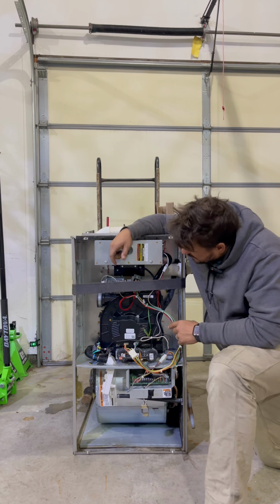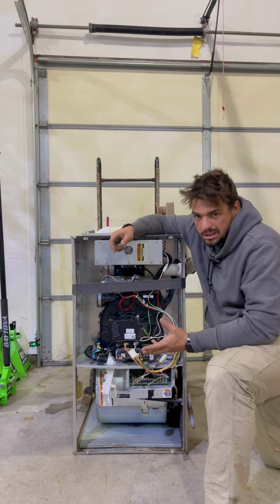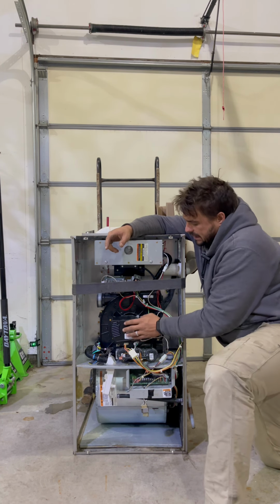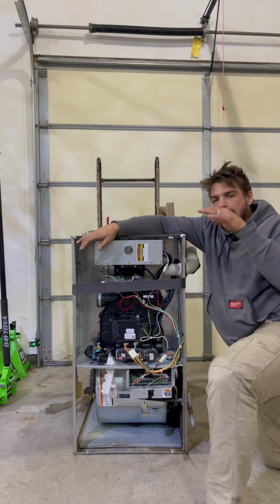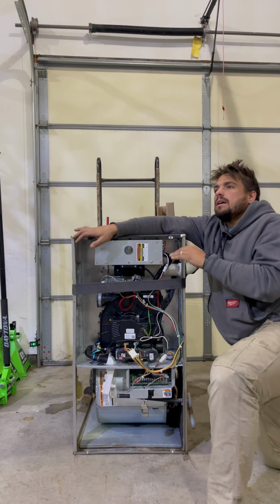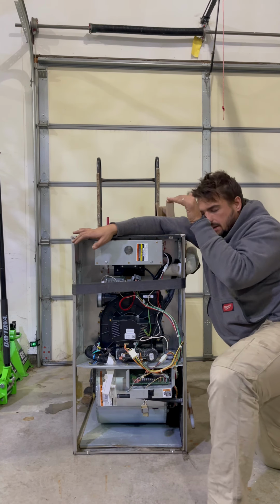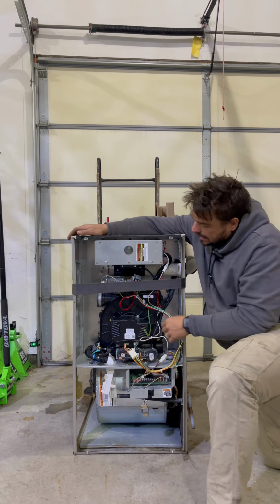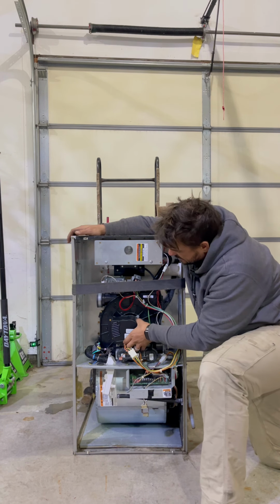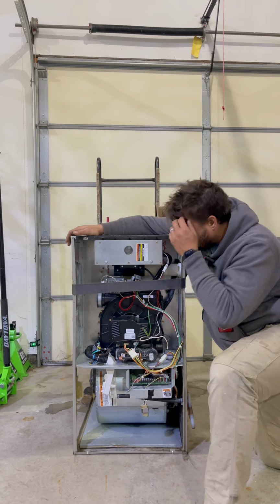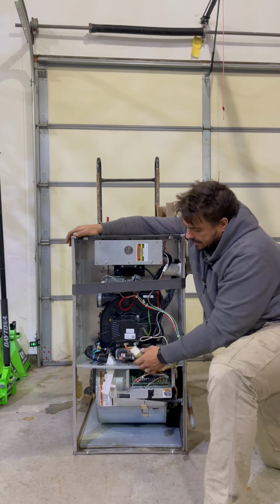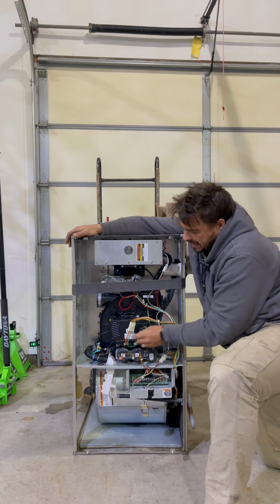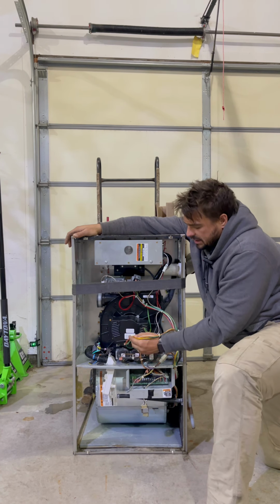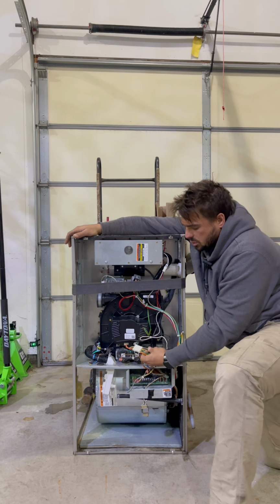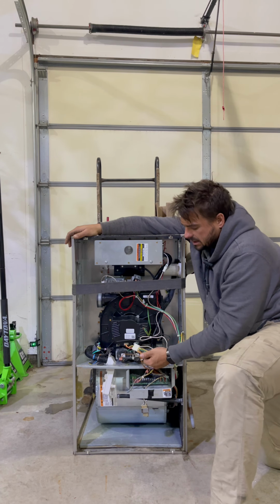This unit is what we would consider a modulating furnace. So instead of just being a high fire or a low fire, it ramps up and ramps down. To do that, these things have a computer chip. If I was to take this off, there's a computer chip in there, and you can see how many wires there are. There's not just a hot and a neutral for on and off, there's all these control wires, speed wires, all that.